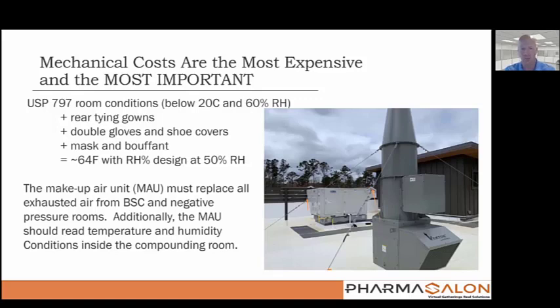USP 797 says we should maintain it below 20 C, and even though it's a recommendation, I can tell you a lot of state boards will say that's a hard must for them. They want to see your temperature and humidity logs consistently below 68 F, which is what we know is 20 C. But if you're running a clean room at 68 degrees Fahrenheit, it's still not going to be cool enough for those technicians, those employees, those pharmacists that are in the PPE.